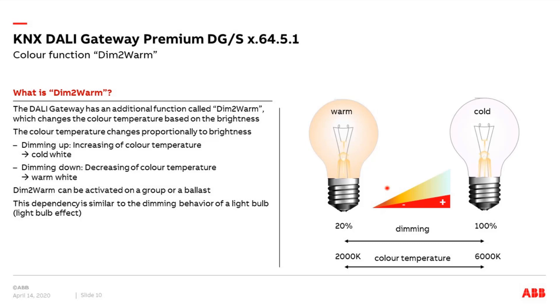The Dim2Warm function can be activated on a single group, single ballast, or multiple groups. It is not a feature of the complete output — we can do it per group. However, only one color function can be assigned per group or ballast: either Dim2Warm or human-centric lighting. You must decide which function that group or ballast will use.